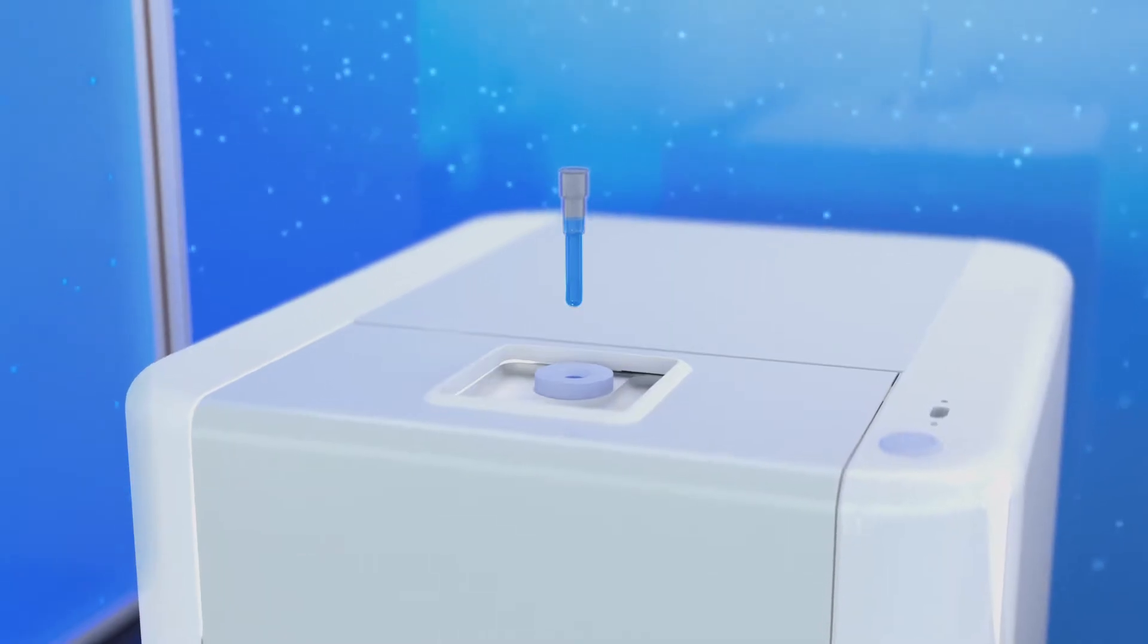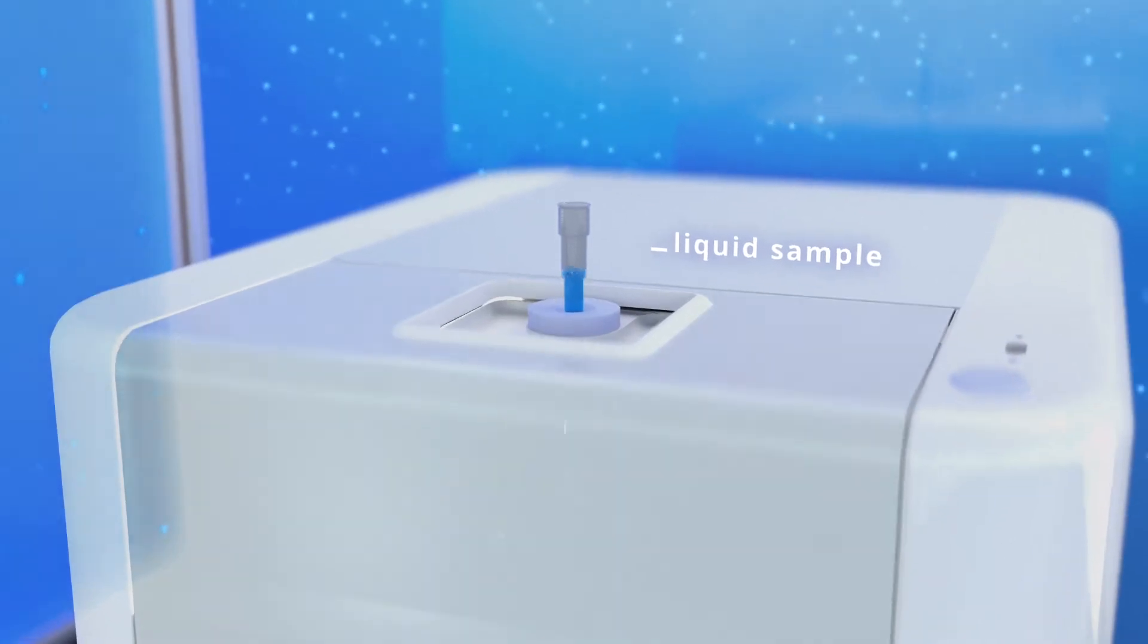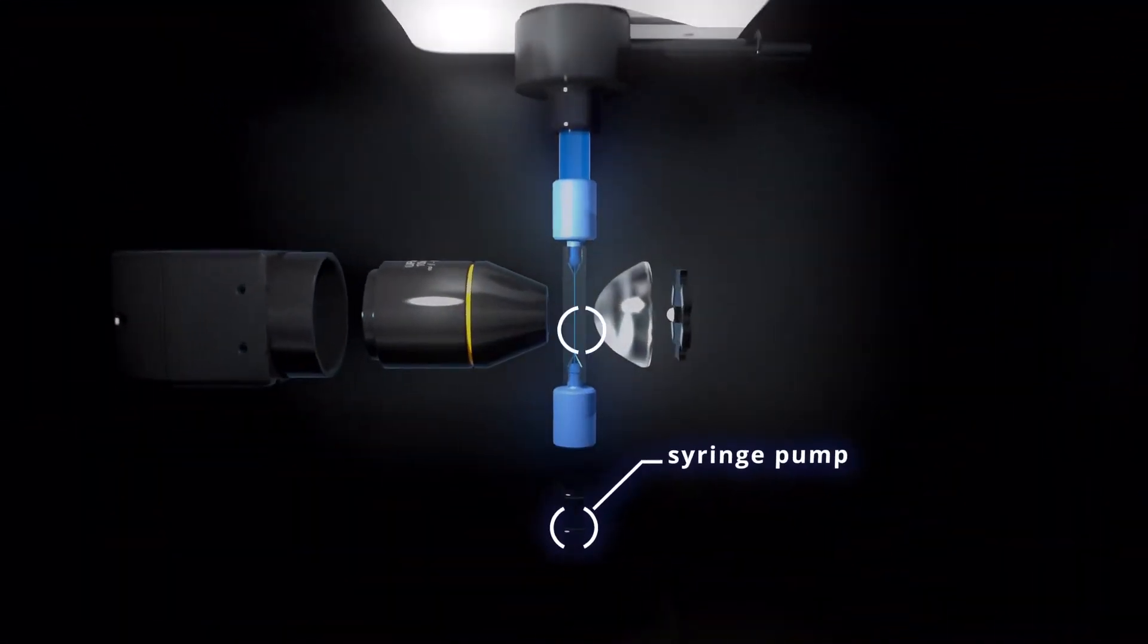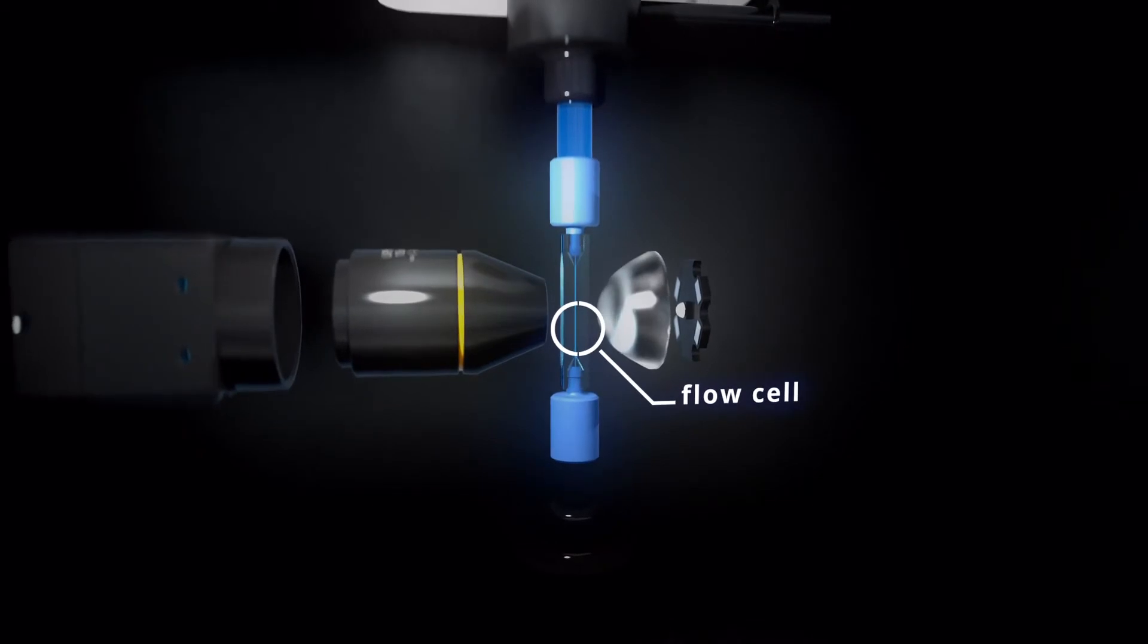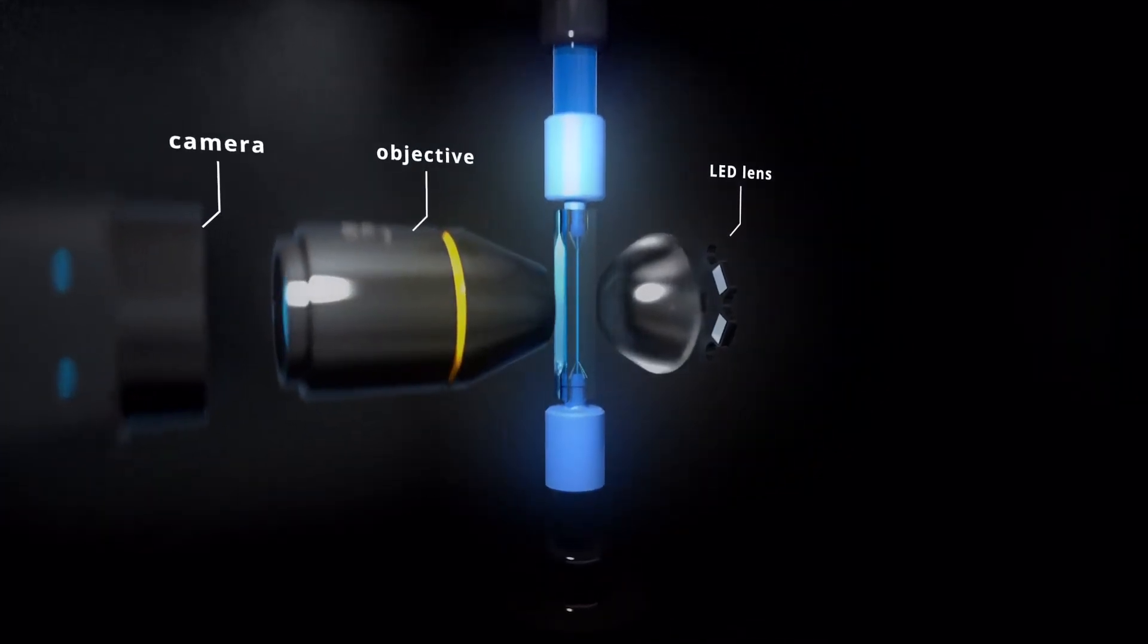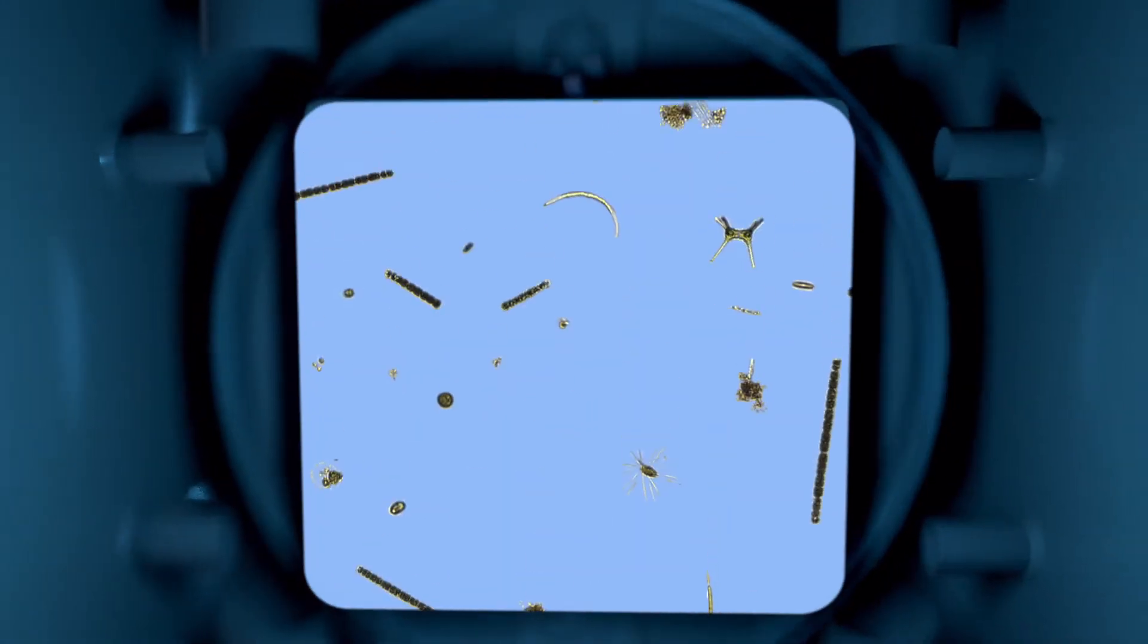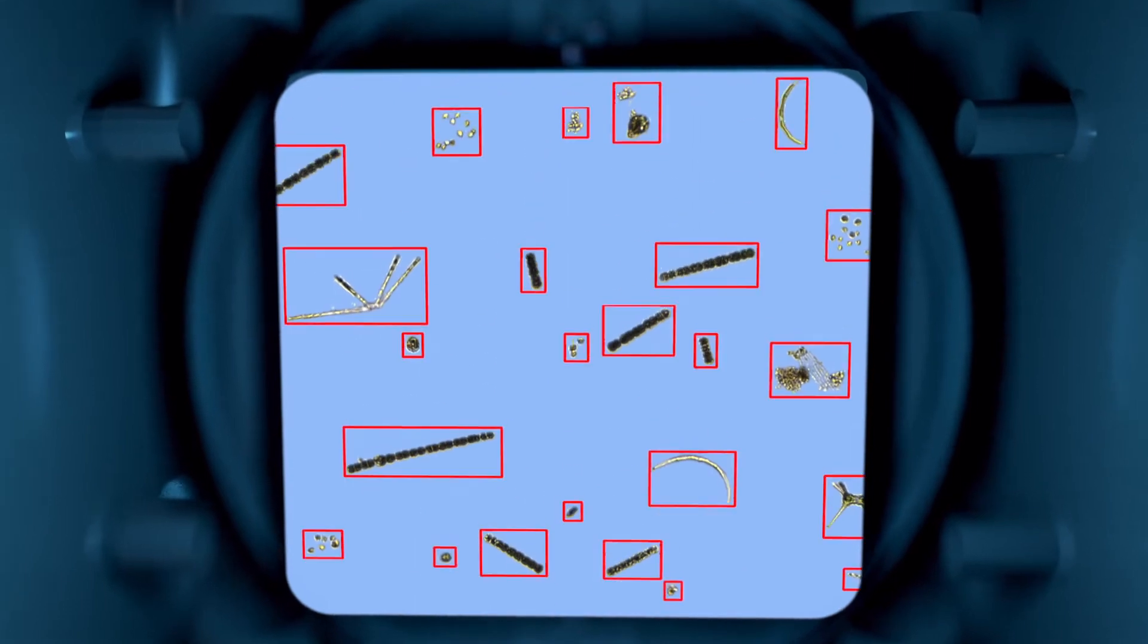After a liquid sample is introduced into the top of the FlowCam, a software-controlled syringe pump pulls it through the flowcell and past the FlowCam's optical system. Using a stroboscopic flash to eliminate motion blur, a camera captures images of algae and other particles in the sample through an objective lens.